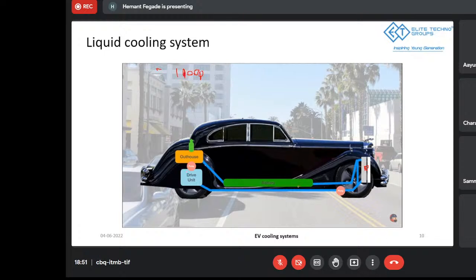In this single loop system, you pass the liquid using a pump through the drive unit, then pump it to the out-house since it's located at the top of the drive unit, and then pass it through the battery pack before retaining it. But the problem with this system is that, being a single loop, we're unable to utilize the maximum efficiency of the liquid, because the liquid gets heated up towards the end and won't be able to convey heat at the optimum range we want.